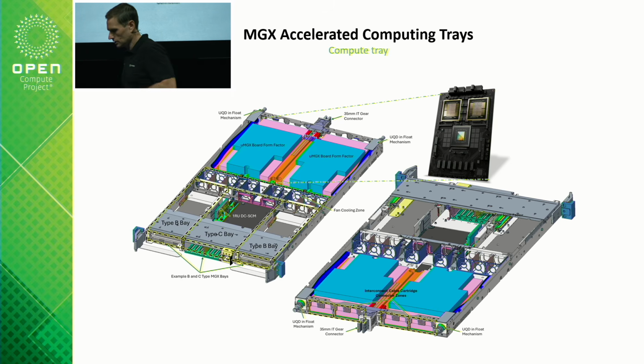We have an inlet on one side, outlet on the other, and in the center is the IT gear connector, also an OCP standard we leveraged, but we needed more power. I mentioned the 8 kilowatts per tray, so we had to put that connector on a diet. It used to be 50 to 55 millimeters wide, we got it down to 35. Doesn't sound like a lot, but it is when you're trying to package all of this connectivity out the back of the trays.